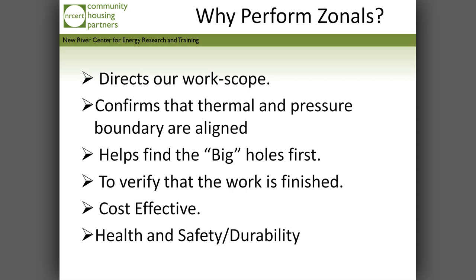It helps us find the big holes first. We don't want to spend hours tracking down 2 CFM of leakage reduction, do we? We want to get in there and knock out several hundred to a couple thousand, get in and get out. That's the key. Get our numbers down quickly, fast. Verify that the work is finished. Test in and test out. Testing out is very important. Testing as you work is important.